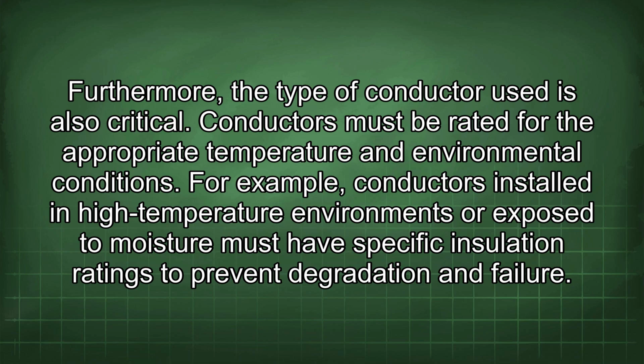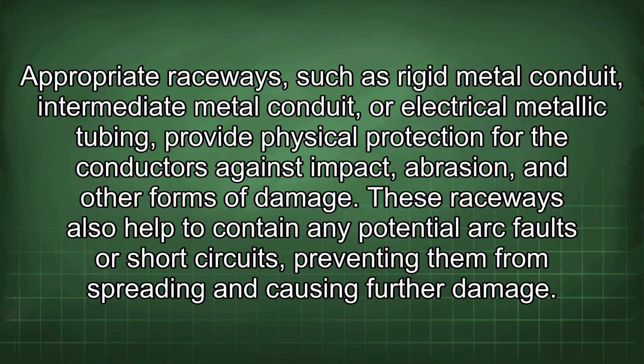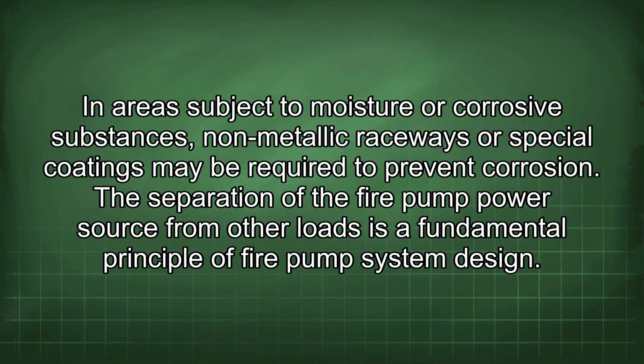Furthermore, the type of conductor used is also critical. Conductors must be rated for the appropriate temperature and environmental conditions. For example, conductors installed in high-temperature environments or exposed to moisture must have specific insulation ratings to prevent degradation and failure. Appropriate raceways, such as rigid metal conduit, intermediate metal conduit, or electrical metallic tubing, provide physical protection for the conductors against impact, abrasion, and other forms of damage. These raceways also help to contain any potential arc faults or short circuits, preventing them from spreading and causing further damage. In areas subject to moisture or corrosive substances, non-metallic raceways or special coatings may be required to prevent corrosion.